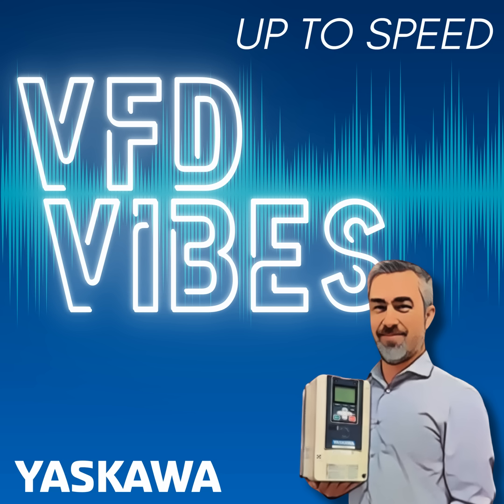And when you talk about a brief overload, you mentioned 150%. In the grand scheme of things, that's small. Often when we're talking available fault current, we're talking tens or hundreds of times the rated amperage of the device. Correct. Overloads are a lot different from short circuits. Overload usually results from something mechanical. You've got something going on with the machine that requires something for a short period of time in excess of the normal load. That's what overload is all about.